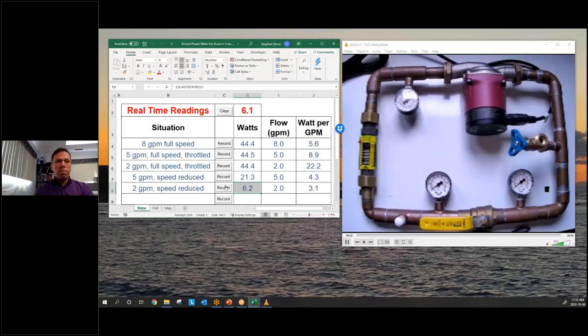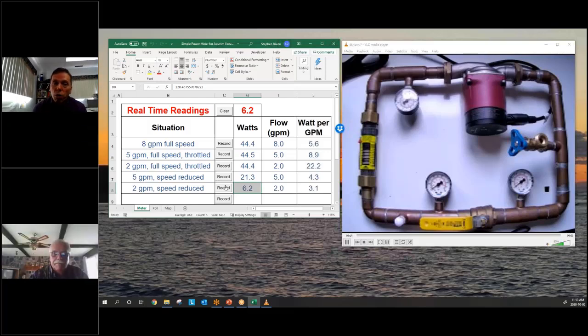And that's where I'll leave the demonstration. Paul, not Paul, but Michelle, did you want to add anything to that one? I know you always get excited about this little demonstration. Yeah, well, since you've upgraded the motor, that has such a large impact on the watt per GPM. The best example for the pressure-driven system is a booster pump. Always be careful. With a booster pump, you may not be able to drop a lot because you need pressure to get that water all the way up to the upper floor.